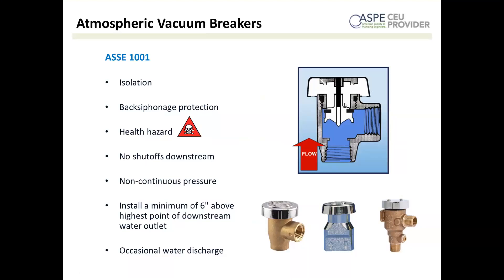You cannot use an atmospheric vacuum breaker for continuous pressure because the vent float can get stuck in the up position if constantly pressurized. Because of that, you cannot put any shutoffs downstream. It must also be installed a minimum of six inches above the highest downstream water outlet, because height is pressure — every foot of water column creates about 0.4 PSI. They can occasionally discharge water, but spill-resistant vacuum breakers are available. Applications include lawn sprinklers, slop sinks, dishwashers, washing machines, and process tanks.